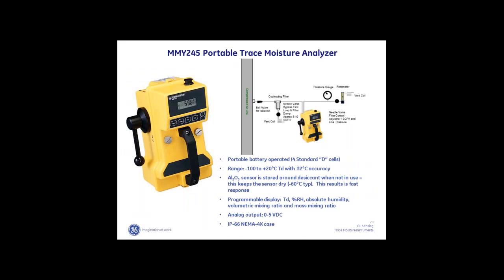Our portables are used for spot checking. The first one is the MMY245 portable analyzer, which has a sensor built into it and an arm that is essentially a valve. When the sensor is not in use, it's surrounded by desiccant which keeps the sensor dry. By pre-drying the sensor, we get a faster response to trace levels because rather than starting from a wet point, the sensor is already pre-dried to approximately negative 60°C dew point or about 10 parts per million. This unit operates on standard D-cell batteries, so you can use it in an industrial plant without needing a special power supply.